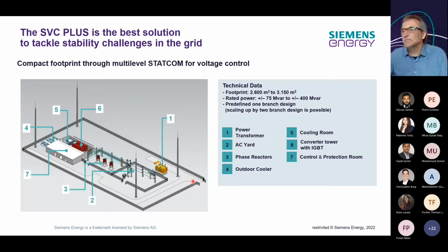If we have a look at the typical configuration of a system, we can see here there's the power transformer. In this case, it's a 3-phase transformer. It could be 3 single-phase transformers. It is connected on the MV bus. We have the phase reactors. These are air core reactors. Just to have them optimized, the most economic one would be the air core reactors.